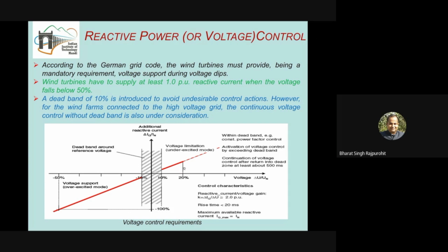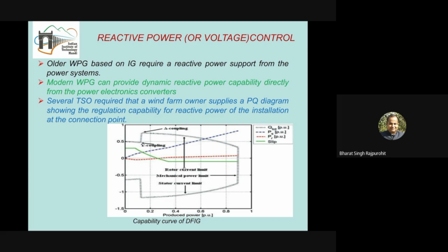So this is a very strict, very severe grid connection requirement that needs to be followed by renewable energy, especially wind, in the case of the German grid code. We do not have such a strict requirement, but broadly a range between 0.9 leading to 0.9 lagging should be possible for a technology to operate, whether SPV or wind turbine. This range is prescribed in the Indian electricity grid code, 0.9 lagging to 0.9 leading. So every technology should be able to operate in this range as per the requirement of the grid. This is what is expected from the Indian electricity grid code.